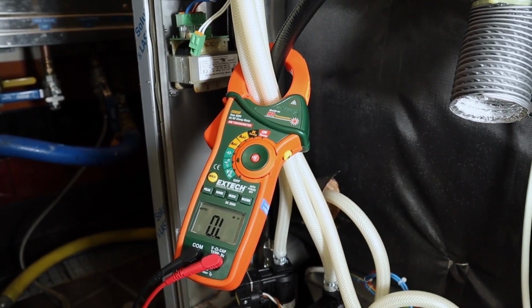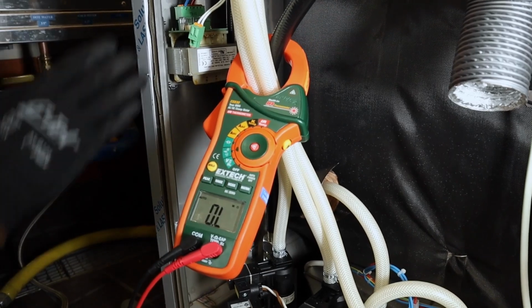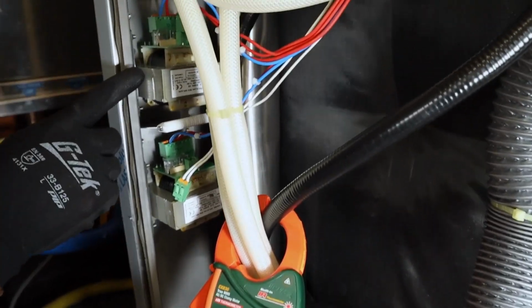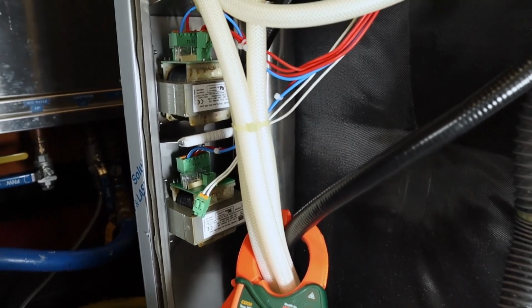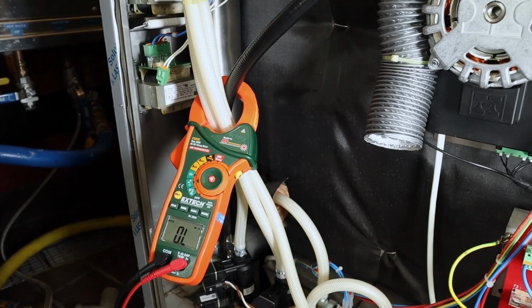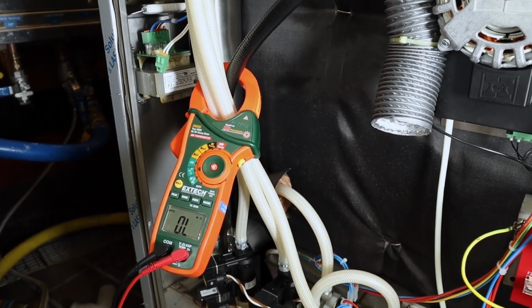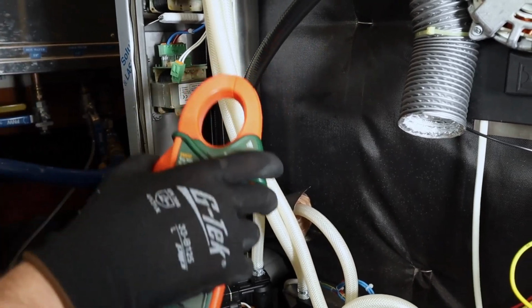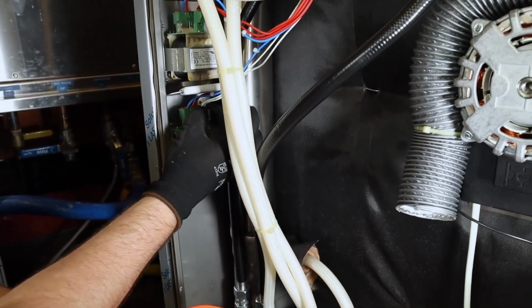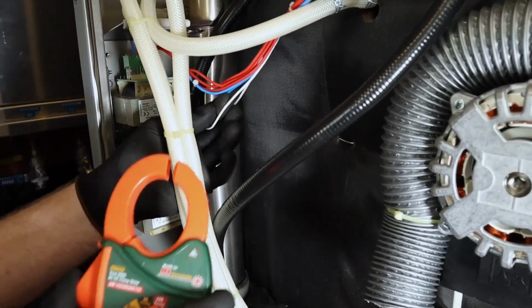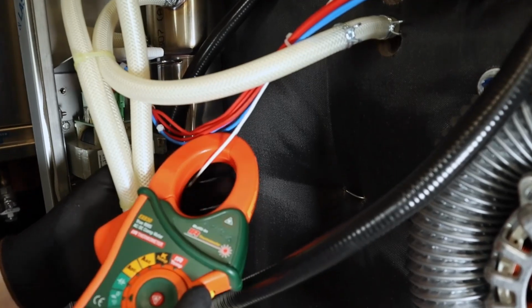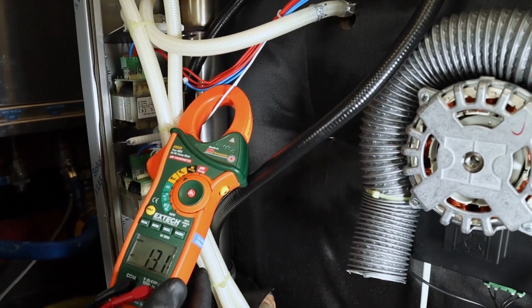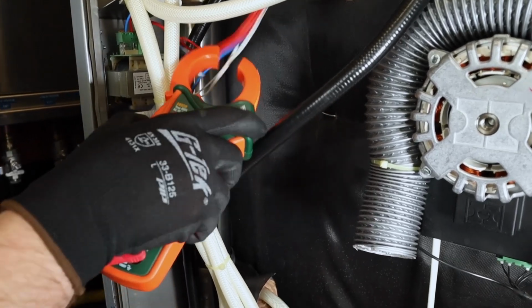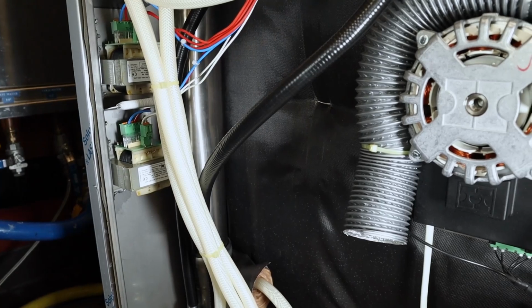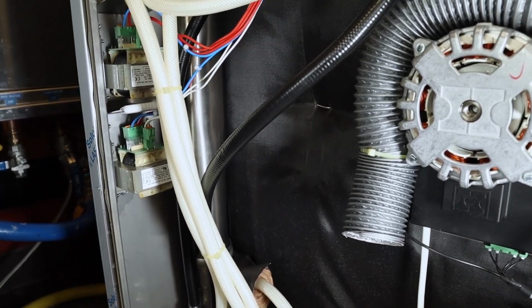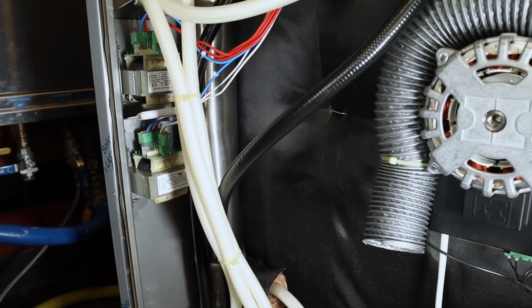Remember, if we're checking a 20 pan, we might need to check both glow electrodes, and that second electrode is going to be right up here on our upper transformer, so we could check it the same. Now, if that is outside of that range and it's higher than 6 ohms, then this would be a good indicator that the glow electrode needs replaced. Also, we can actually check amp draw on that glow electrode too, with it plugged back in like so. You may need to cut a couple zip ties, but we can put our amp clamp around the glow electrode wire, switch over to AC amperage, and then we're going to be looking for at least 1.4 amps on that glow electrode when we start the cook cycle and it's starting to glow. So we need to have at least 1.4 amps there when we're checking that.